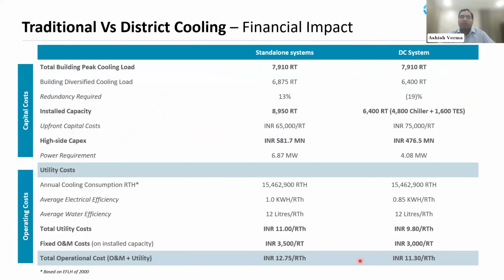This is the financial impact when we compared both the systems, standalone versus DC systems. Considering upfront, first is the capital cost, because obviously the standalone cooling systems are a bit cheaper. That's why the cost is lower per RT. But DC systems are costlier per RT. But when you consider the high side capex here, the DC system cost is lower than the standalone cooling systems. The main reason for that is the lower installed capacity, and even power demand is 4 megawatt as compared to 6.87 megawatt for the standalone cooling systems.